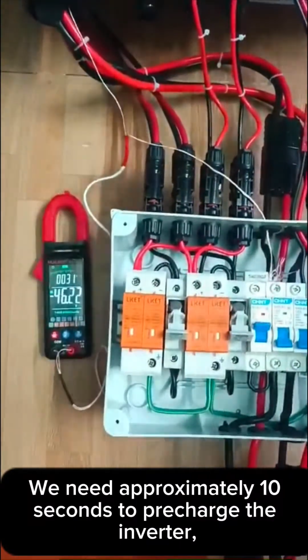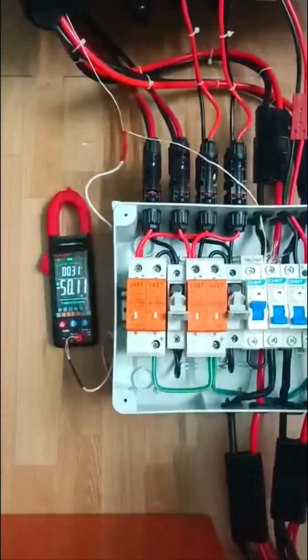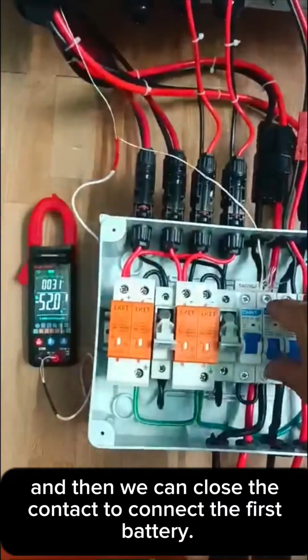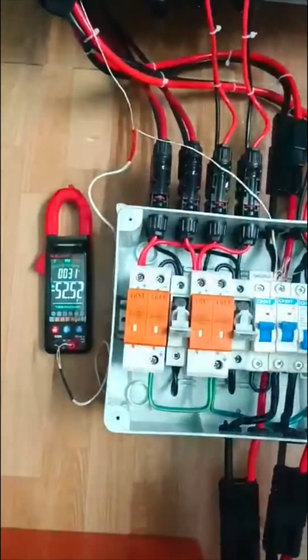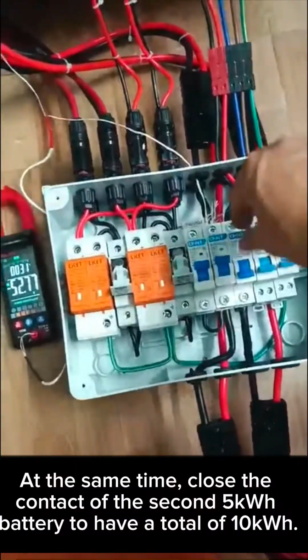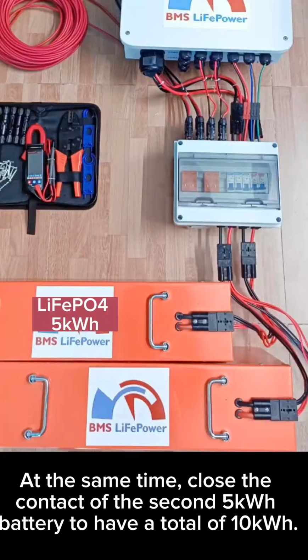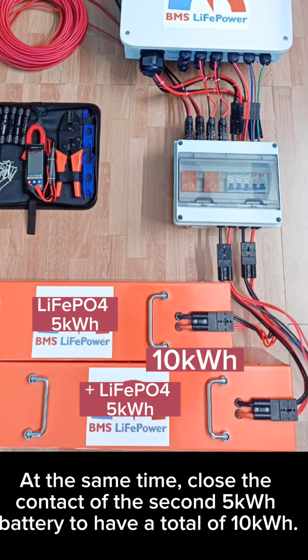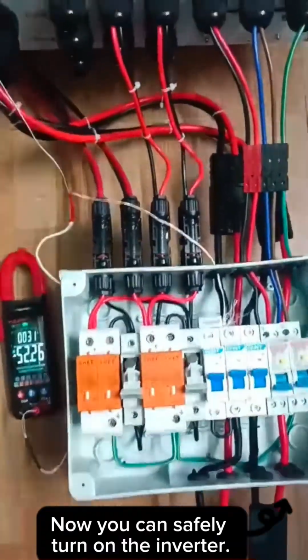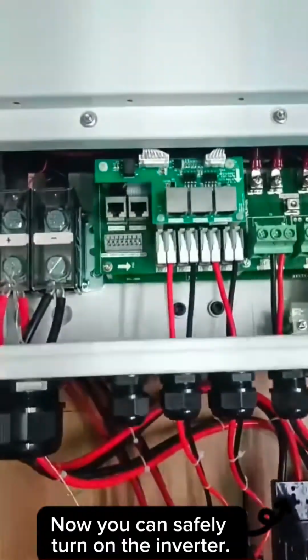We need approximately 10 seconds to pre-charge the inverter, and then we can close the contact to connect the first battery. At the same time, close the contact of the second 5 kWh battery to have a total of 10 kWh. Now you can safely turn on the inverter.